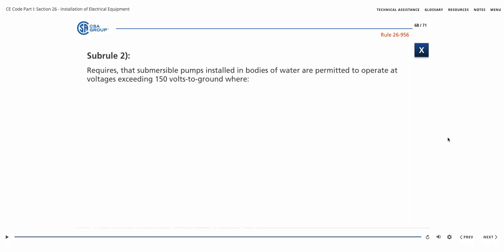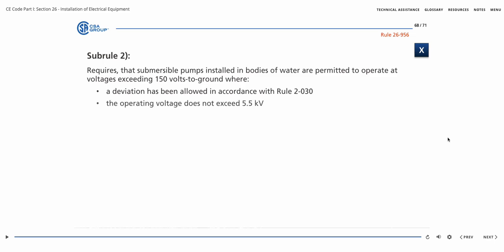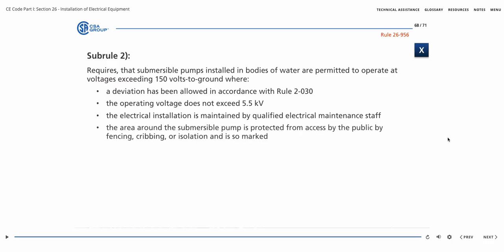Sub-Rule 2 requires that submersible pumps installed in bodies of water are permitted to operate at voltages exceeding 150 volts to ground where a deviation has been allowed in accordance with Rule 2-030, the operating voltage does not exceed 5.5 kilovolts, the electrical installation is maintained by qualified electrical maintenance staff, and the area around the submersible pump is protected from access by the public by fencing, cribbing, or isolation and is so marked.